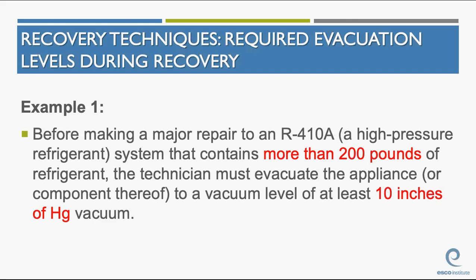Okay? More than 200 pounds of refrigerant. Let me tell you, that is a large amount of refrigerant. Okay? But because it actually says in here, or a component thereof. In other words, if I have a supermarket rack system running 410A, which I just don't understand why I would have, and if I just need to replace one compressor, I'm not going to evacuate the full 200 pounds of refrigerant. I'm just going to evacuate what's in that compressor. But I have to evacuate it to 10 inches of mercury. Okay, pretty direct and to the point.